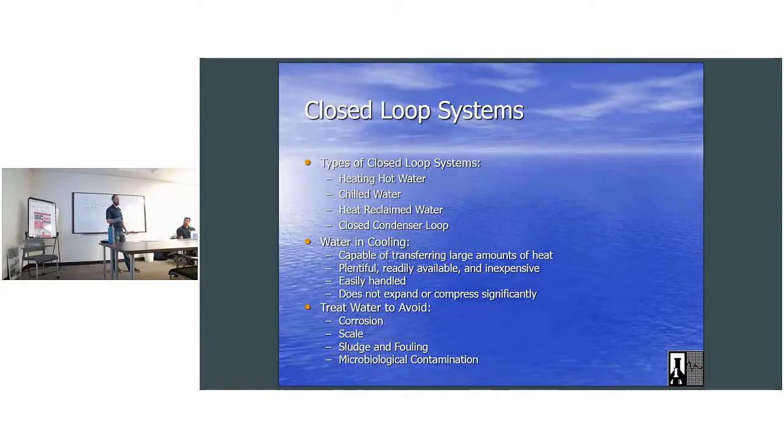A good thing, if it's dirty, is you could drain the loop completely and then fill it with a flow meter, and then you'd know. That's a good idea. If you're already doing a running flush anyway, if it's really dirty, hasn't had treatment in a while, and it's muddy, just do a running flush, and then when you fill it, dump it. It might not be completely accurate because some of your horizontal lines or coils aren't going to drain all the way, but you'll get close enough to know, especially if you're going to put glycol in it. But that's the other way we can do it.